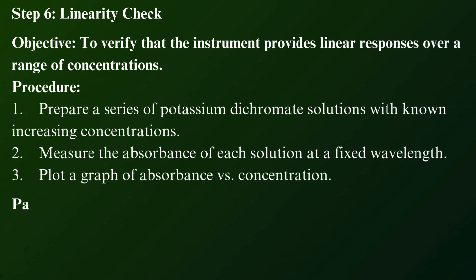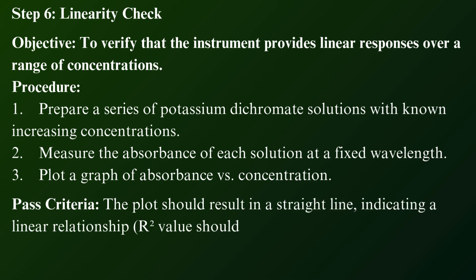Step 6: Linearity check. To verify that the instrument provides linear responses over a range of concentrations. Procedure: Prepare a series of potassium dichromate solutions with known increasing concentrations. Measure the absorbance of each solution at a fixed wavelength. Plot a graph of absorbance versus concentration. Pass criteria: The plot should result in a straight line, indicating a linear relationship.